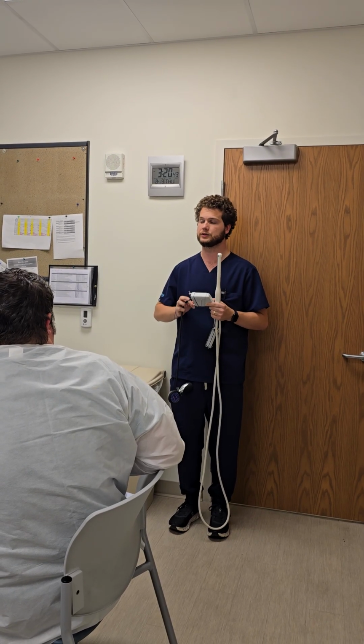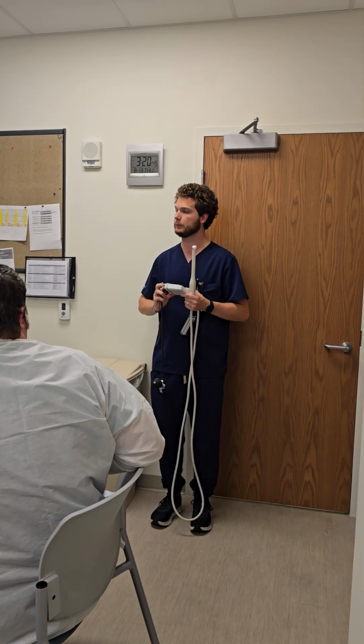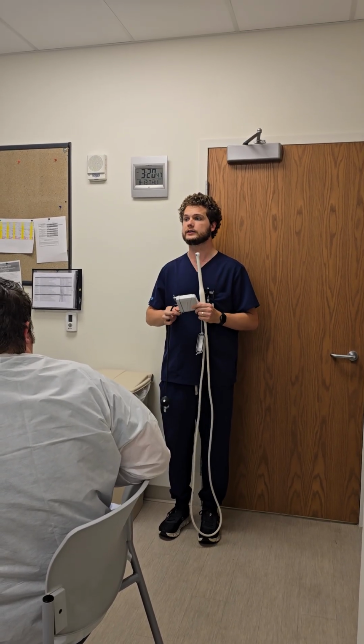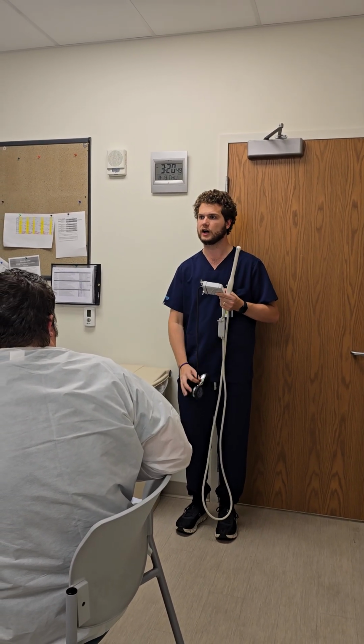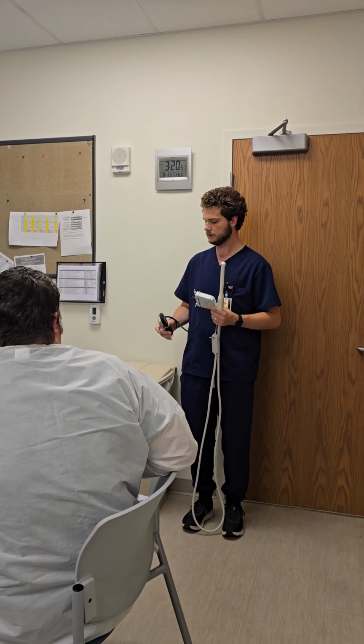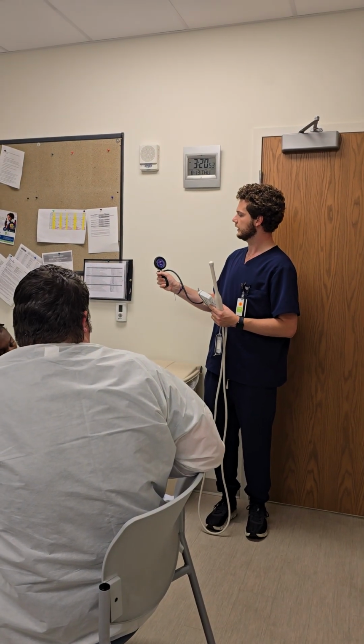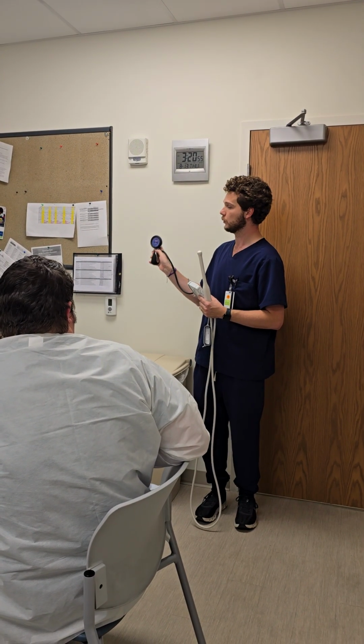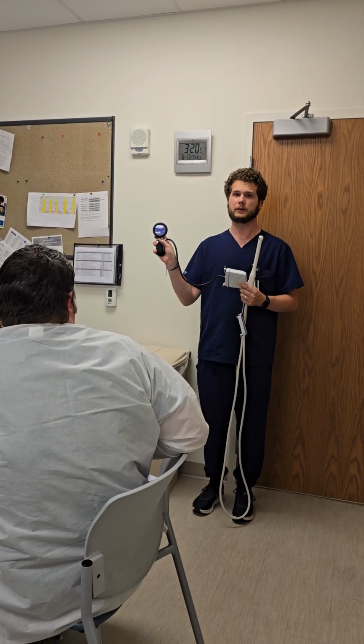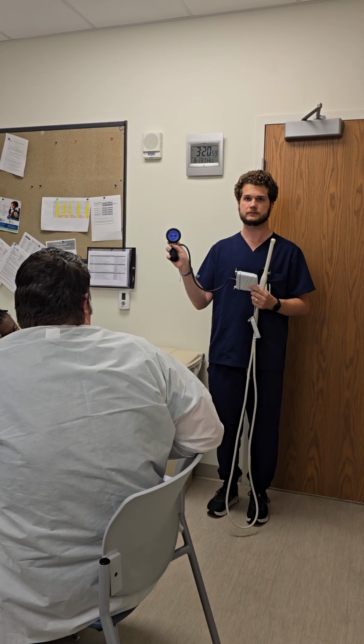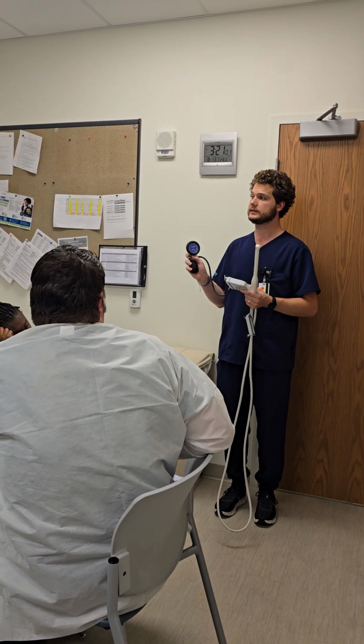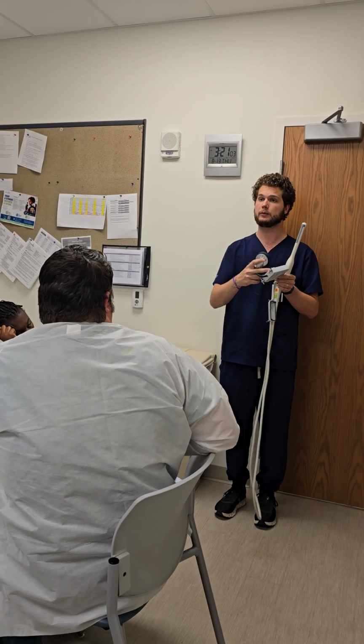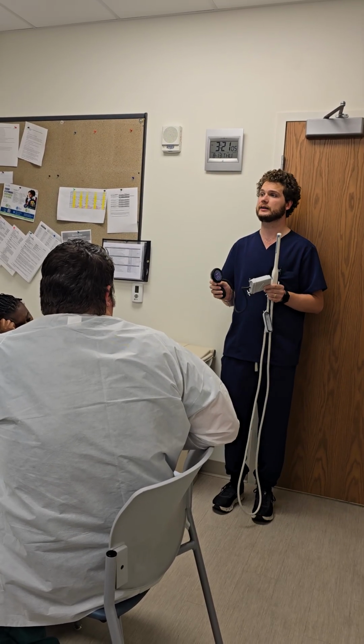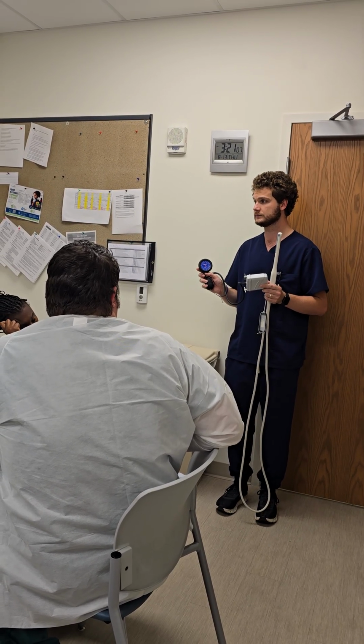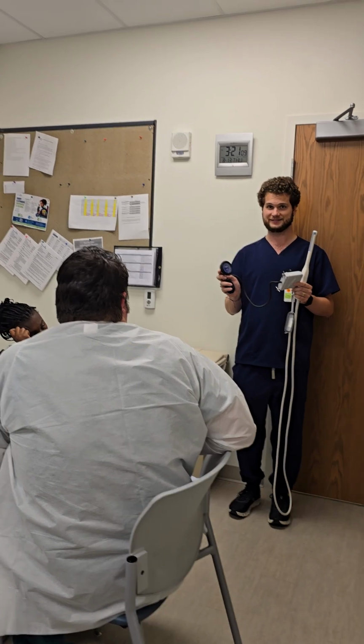For the wet test, we're going to do the same thing. We're going to reduce it, blow it back up to 150, put it under water. We're going to watch for about 45 seconds. So we pump it up, take it to that 150 marker, which is right in the middle, and just watch it. Most of the time, it's just going to stay in the same place. So that's okay. When you do the wet test, make sure that there's no bubbles coming out of the cap. If there's bubbles coming out, it is an instant fail. Any questions on the leak test?